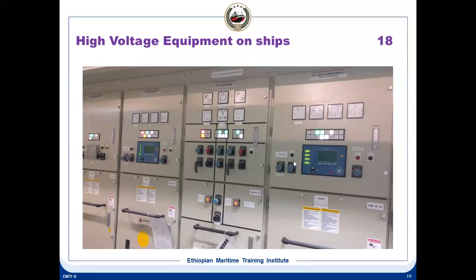It's a power management system on both. Here you can simulate all these things. If you want to do reverse power trips or any other trips, you can set on this HIMAP system at what kilowatt you want it to trip. So all those things can be done here. In this you can see a lockout relay here. Here this is a lockout relay. All the trips, everything, is connected with a lockout relay. It's the final relay which trips the breaker.